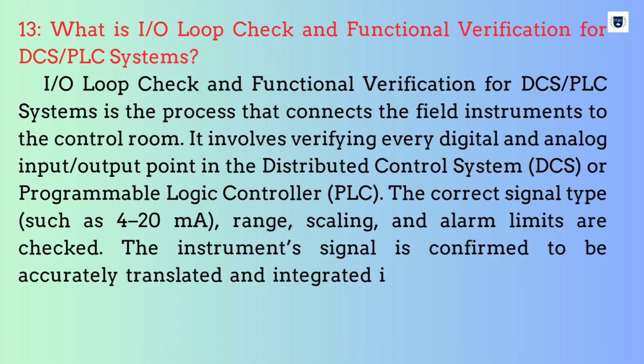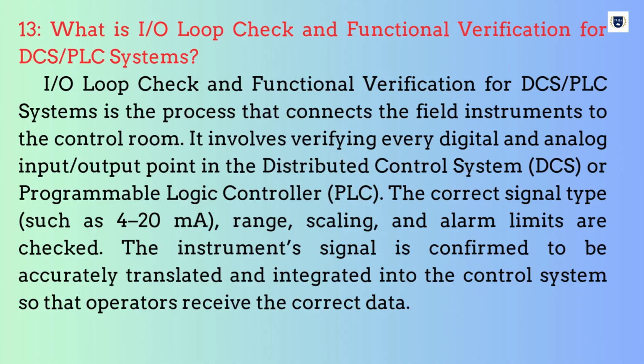What is I/O loop check and functional verification for DCS PLC systems? I/O loop check and functional verification for DCS PLC systems is the process that connects the field instruments to the control room. It involves verifying every digital and analog input-output point in the distributed control system (DCS) or programmable logic controller (PLC). The correct signal type, such as 4 to 20 milliamps, range, scaling, and alarm limits are checked. The instrument's signal is confirmed to be accurately translated and integrated into the control system so that operators receive the correct data.